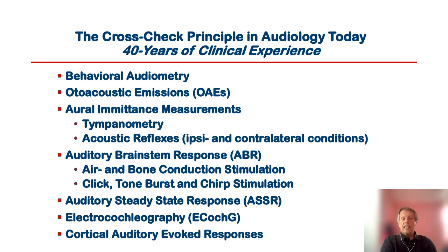Now, in addition to the ABR, we have the auditory steady state response. The auditory steady state response, or ASSR, provides us with the opportunity to present very high intensity stimuli and to record a response that is automatically detected. It doesn't require visual inspection of a waveform. It's automatically detected and statistically confirmed.